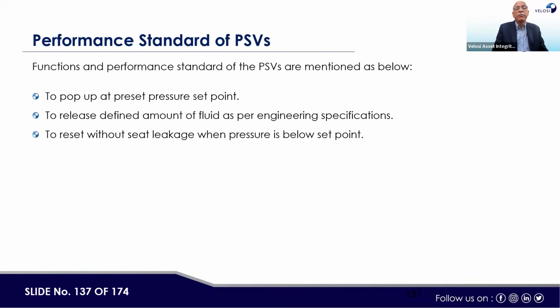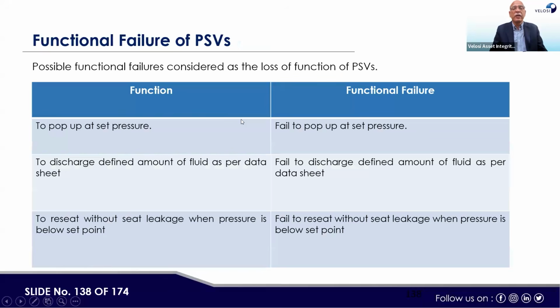Then here the functional performance standards for PSVs are mentioned as below: to pop up at preset pressure set point, to release a defined amount of fluid as per engineering specification, and to reset without seat leakage when pressure is below the set point. These are the normal functional performance standards. Then the possible functional failure is considered as a loss of the function of the PSV: fail to pop up at set pressure, fail to discharge the defined amount of fluid as per data sheet, and fail to reseat without seat leakage when pressure is below the set point.